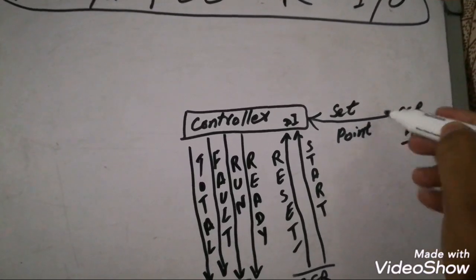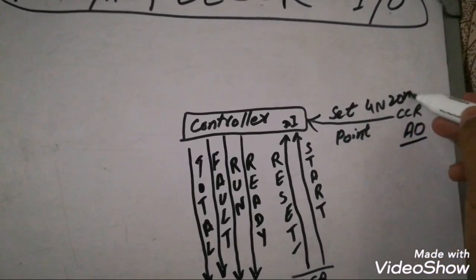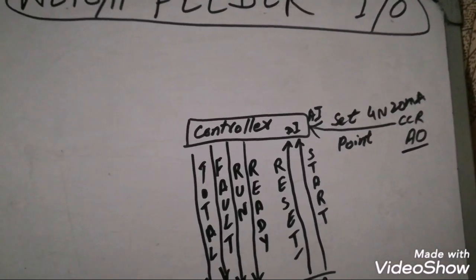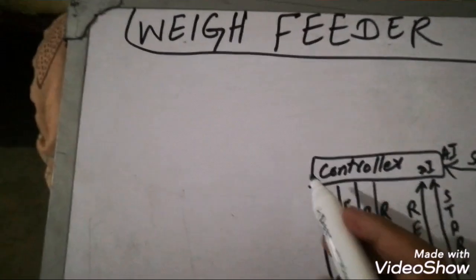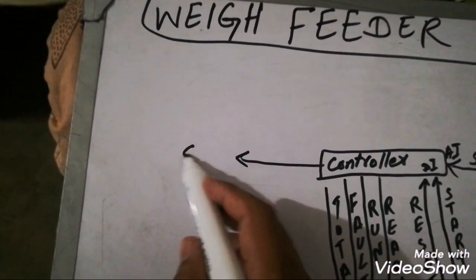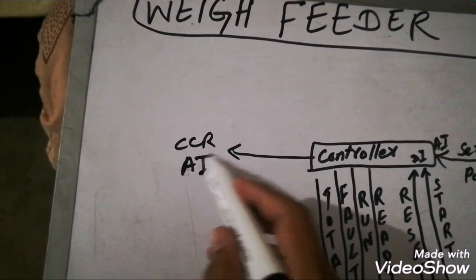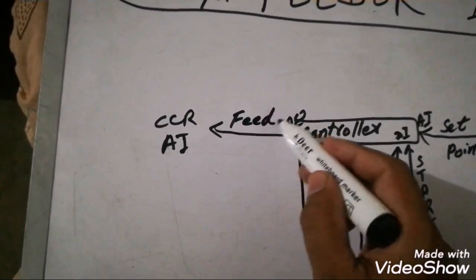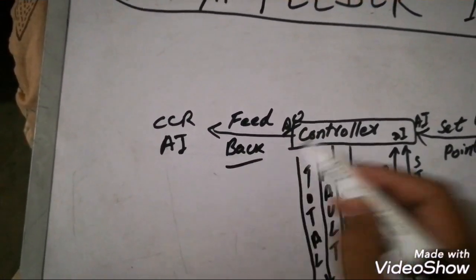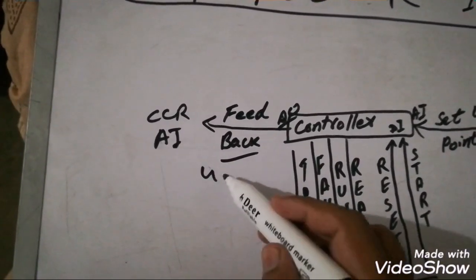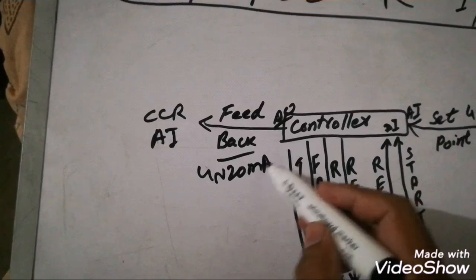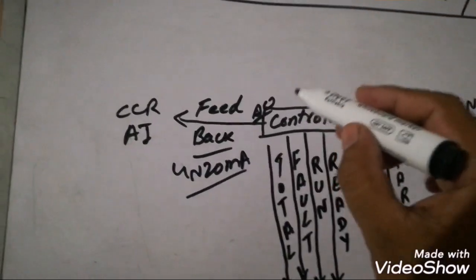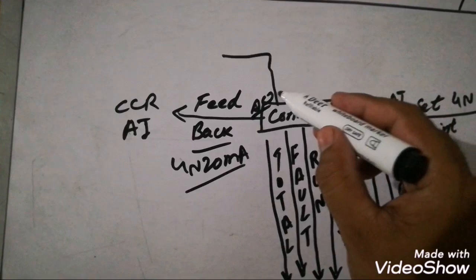There is a CCR analog output which is the set point of the controller — how much material we need from the weigh feeder. This set point is 4 to 20 mA. The analog output of the controller, which is the CCR analog input, is the feedback of the weigh feeder showing how many tons or kg are passing per hour. This is also 4 to 20 mA and represents feedback to the operator in ton per hour.